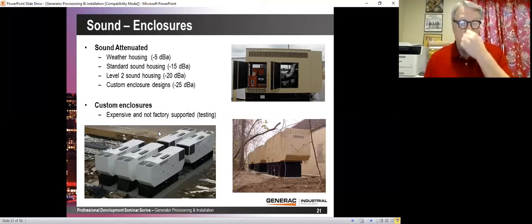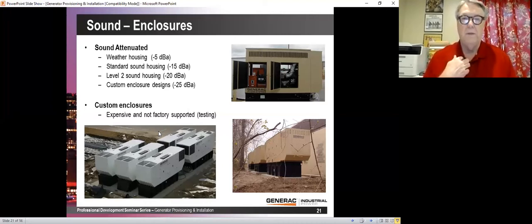For instance, on generators used in the cinema, they're filming outdoors. They can't have the generator sound on the soundtrack, and the enclosure can cost you a lot more than the generator. Now, I would not use these dBA levels. These are maybe typical, but it varies all over the place depending on what the generator is. So don't assume those dBA values are accurate, but every manufacturer can give you a test sheet that shows exactly what their dBA is, and that's the way you should look at sound, not by looking at what the sound of the muffler is.